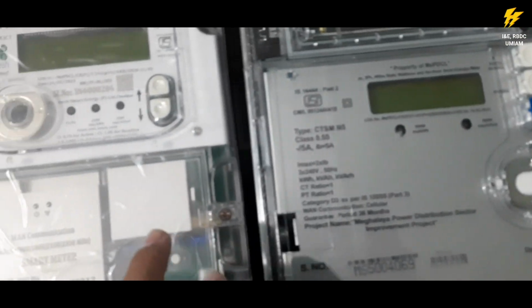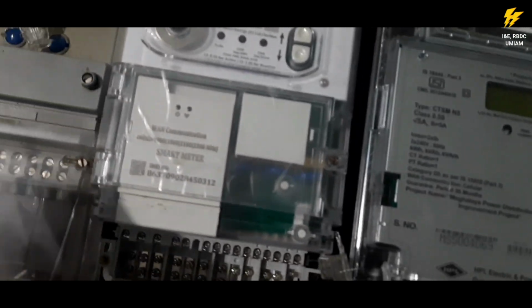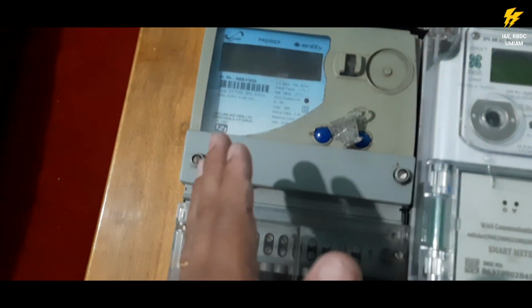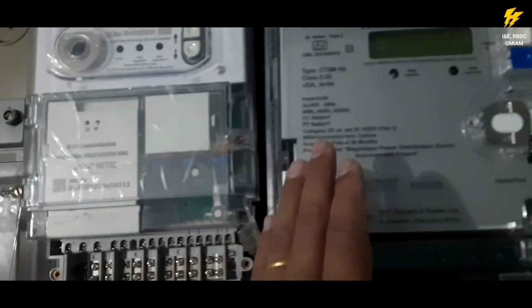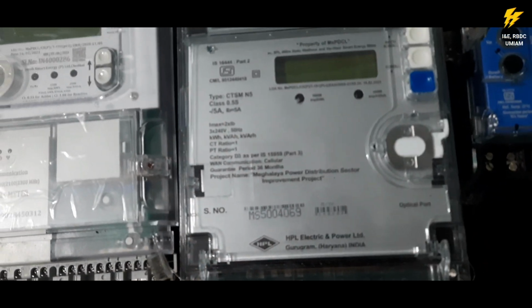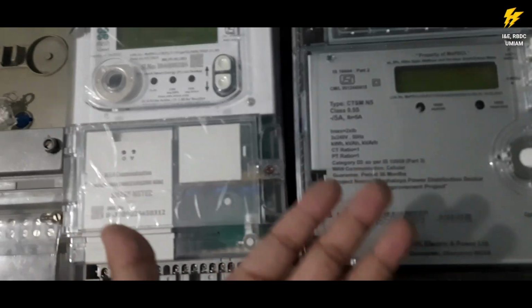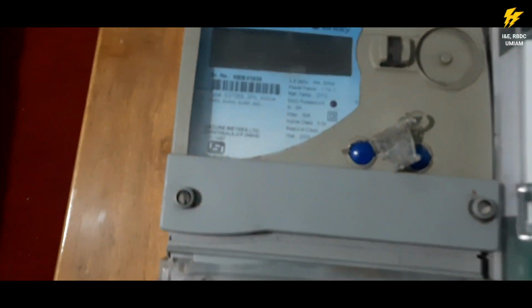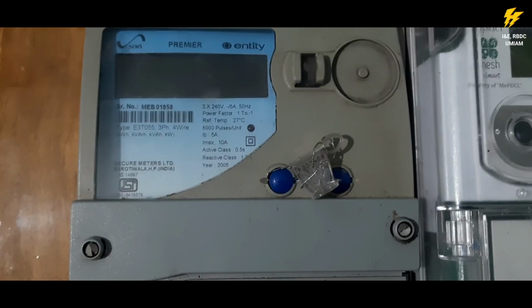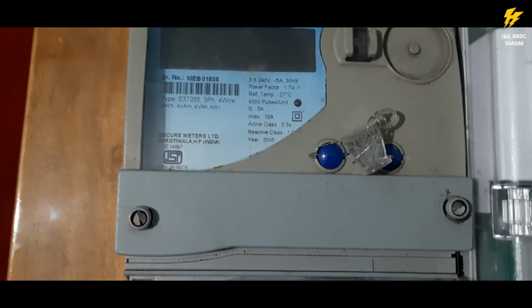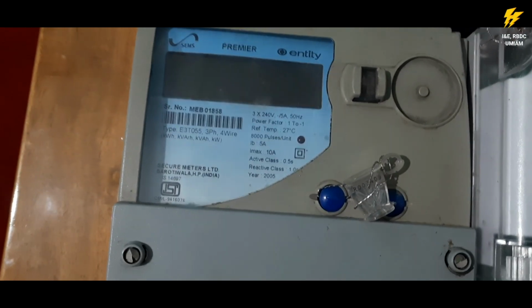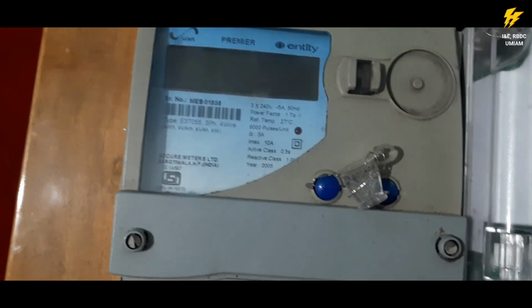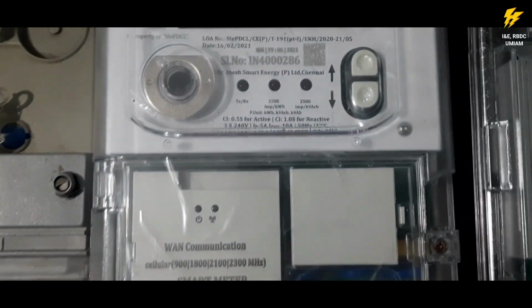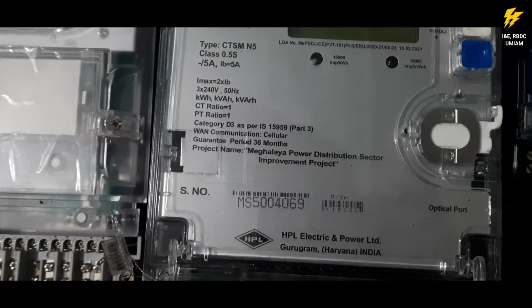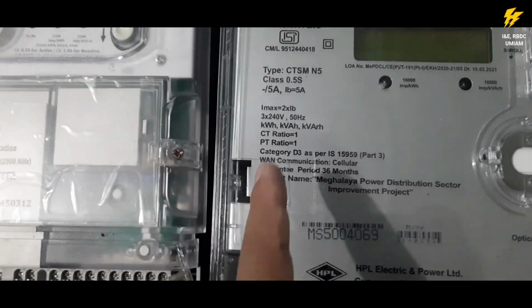Now the accuracy class - out of the Secure, this Inage smart meter, and this HPL meter, which one is more accurate, as claimed by the company? We will see the Secure meter's accuracy class is 0.5s. That means if the percentage error as claimed by the company is less than 0.5%. This one is slightly more, it's 1%, and HPL is 0.5, less than 0.5%, because it's class 0.5s.